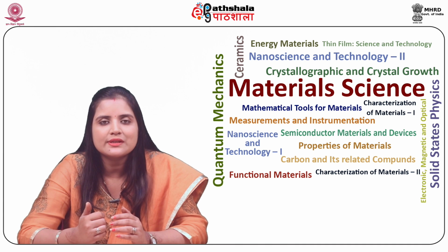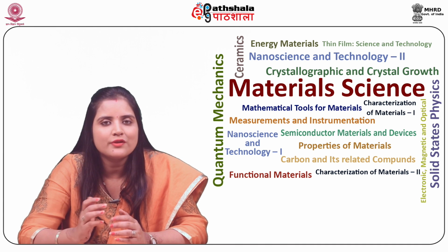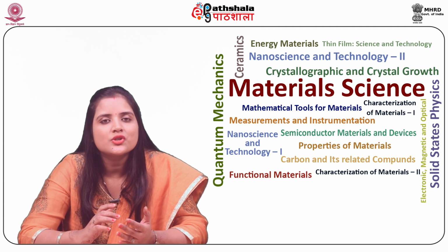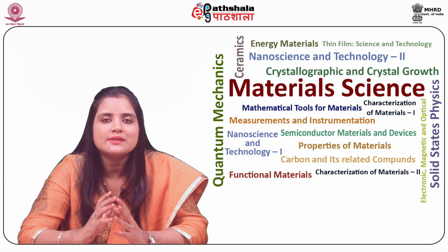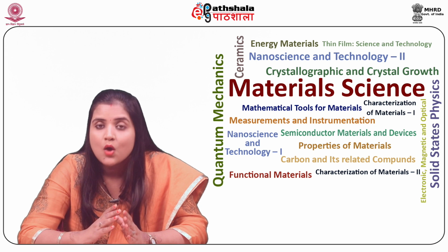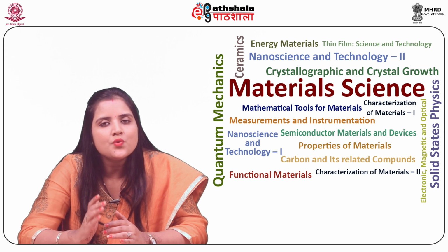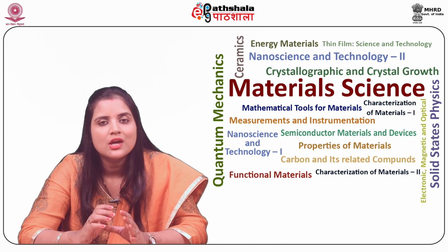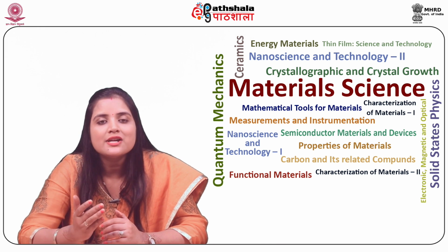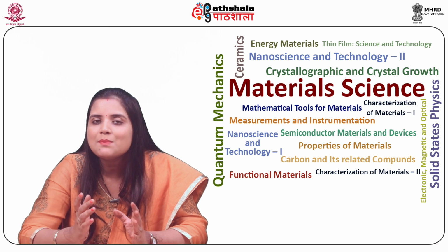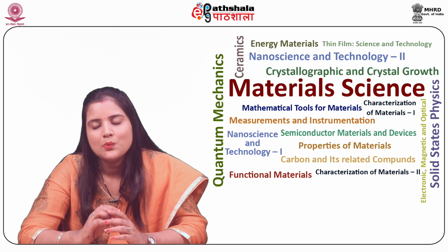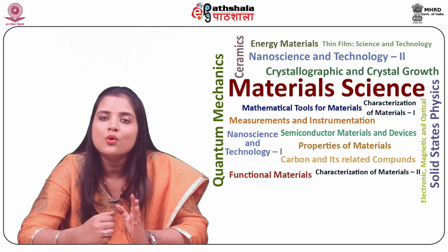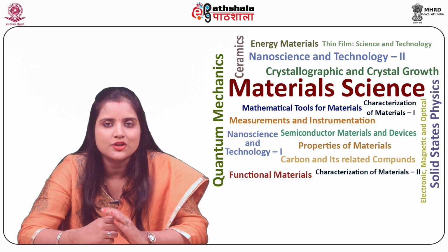Let us now discuss the source of illumination. The source of light which is used is a continuous type, that is a 150-watt ozone-free xenon arc lamp. The lamp's light is accumulated by a diamond turned elliptical shaped mirror, which is then focused onto the excitation monochromator's entrance slit.